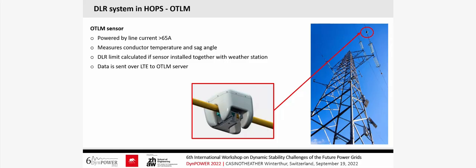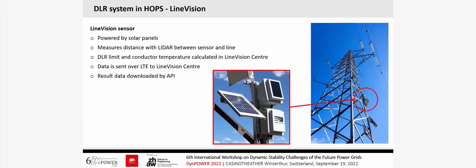The other system is installed on the tower and has a LiDAR sensor that measures the distance from the line. If the line gets hotter, the sag will be bigger and the line will be closer to the tower. The data is sent to the line vision center, which calculates the DLR limit, and we download the data via API or internet.